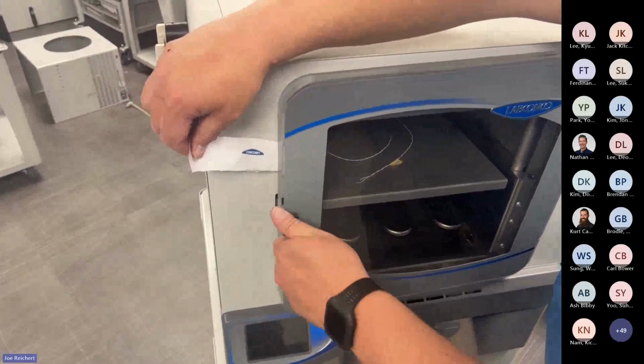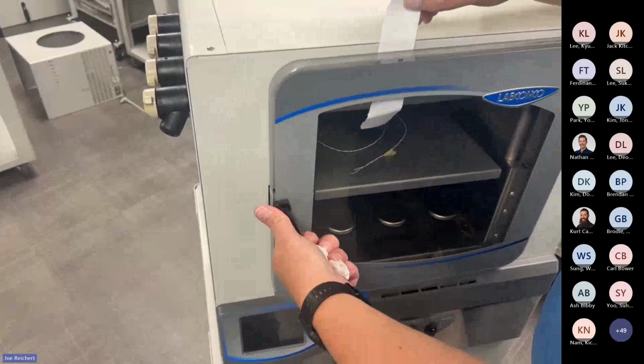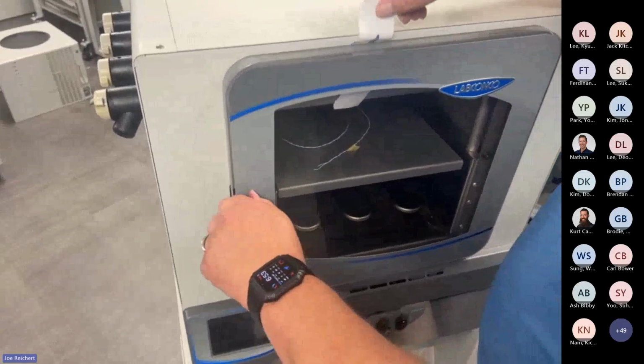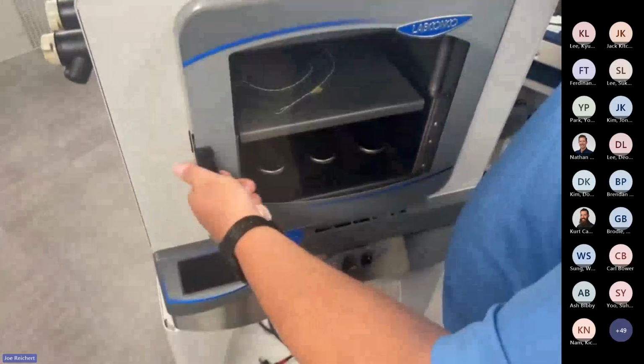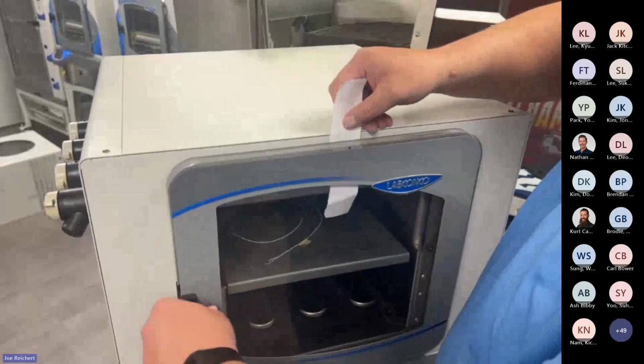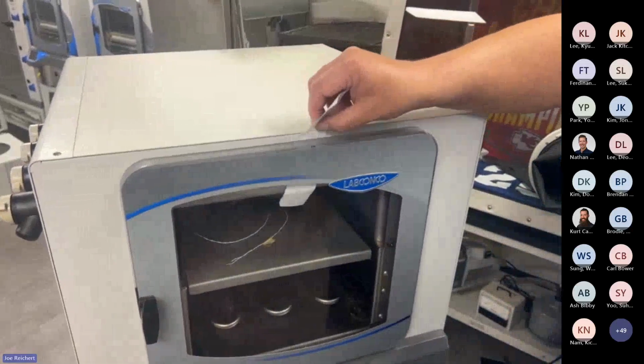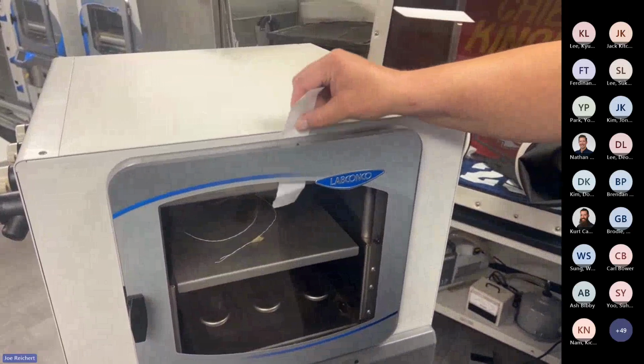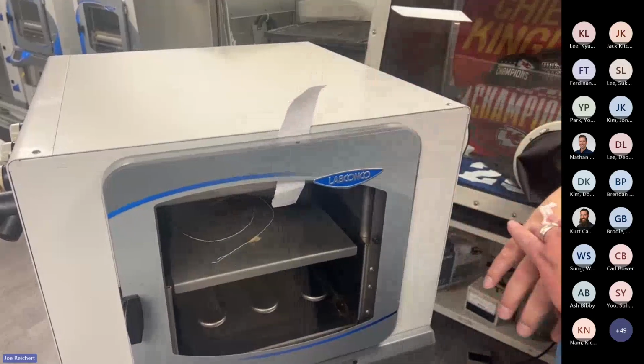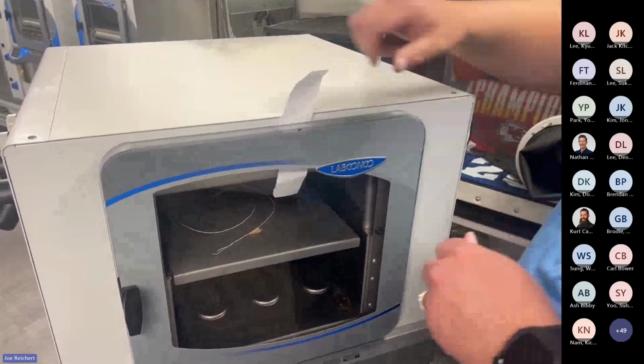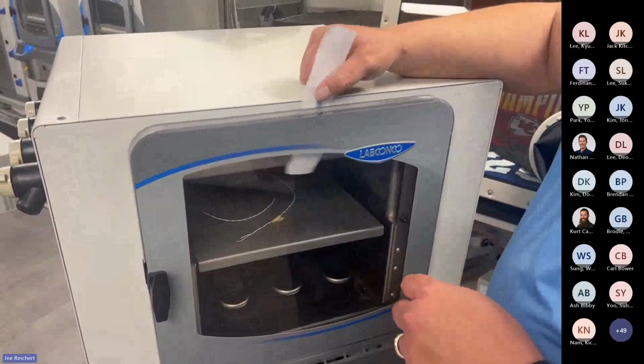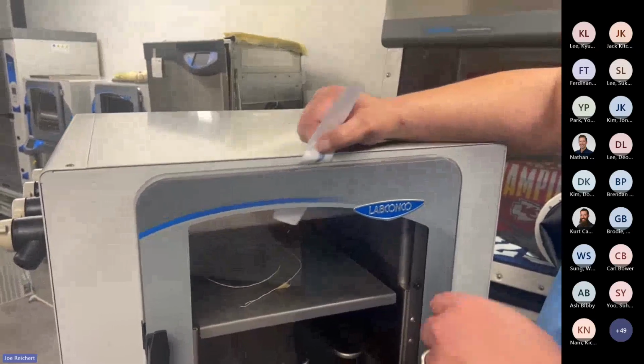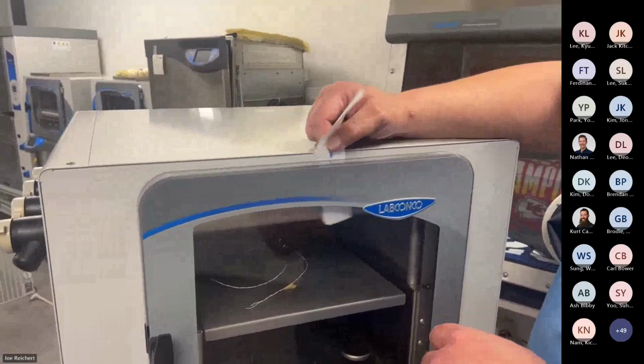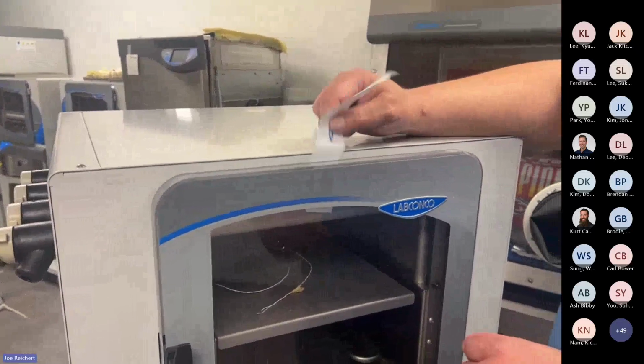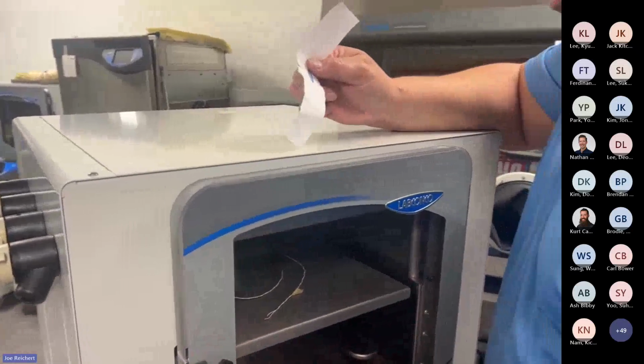It's all tight. But this unit we found actually has a spot at the top. See how easy that slides out of there? Shouldn't be able to push the paper through the gasket. So we believe on this unit, it actually has a bowed door. So the issue isn't with the gasket or the frame, it's the door itself. And you can slide that through there. It shouldn't be able to do that. So this would probably leak right there at that spot.